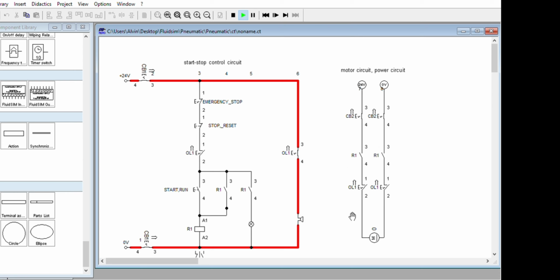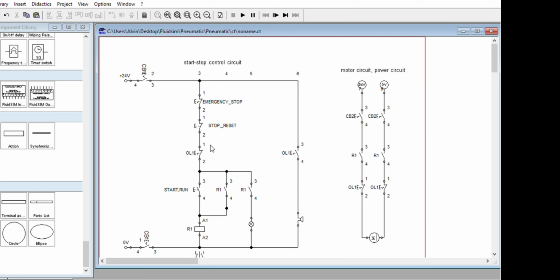So no more power. Why? Because that is turned off. Auxiliary is controlling that power contacts. So it is now open because the relay has no supply. The supply now is in the alarm system. You can have lamps also there. The right thing to do is turn off the main CB and see what causes the overcurrent. Turn off the whole circuit. That's the time you are going to reset the thermal overload relay, if you are reviewing the causes of the overcurrent in the motor circuit.